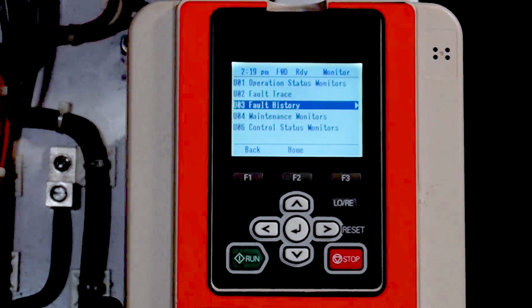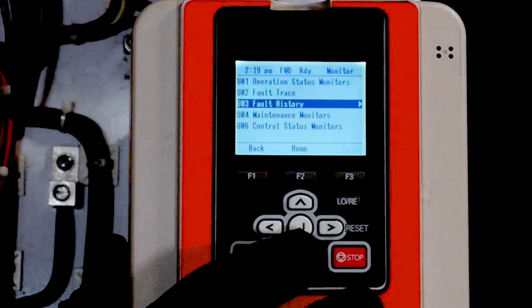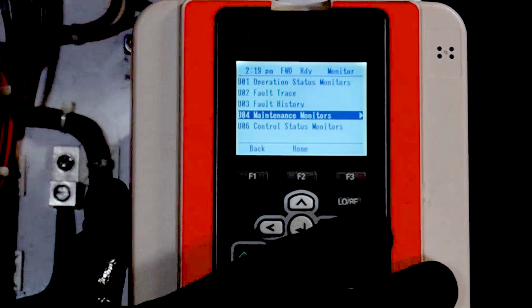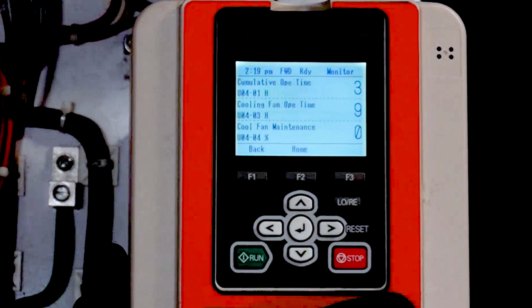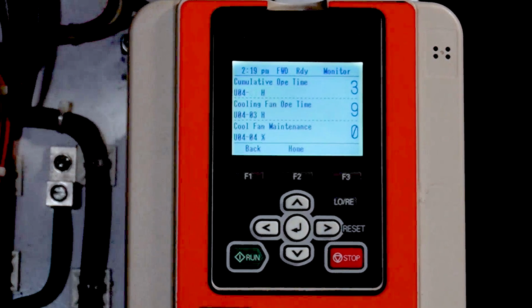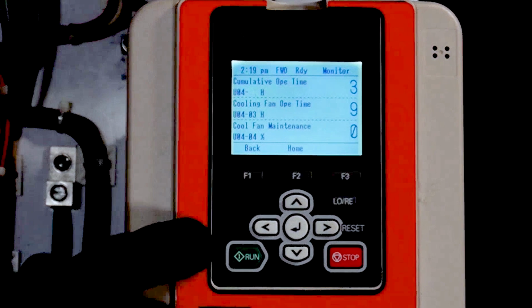I'm going to back out. Okay, there is the maintenance schedule brought out here. That's the U04. Some people use this to determine when it's time to service the drives, for an inspection of the electricals on the crane, as well as maintenance such as greasing bearings, checking couplings, and brake linings, and so on. All right, so that's those.